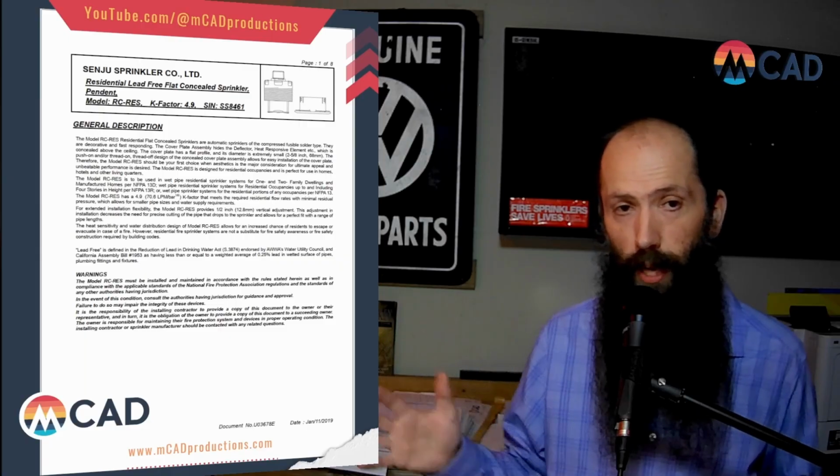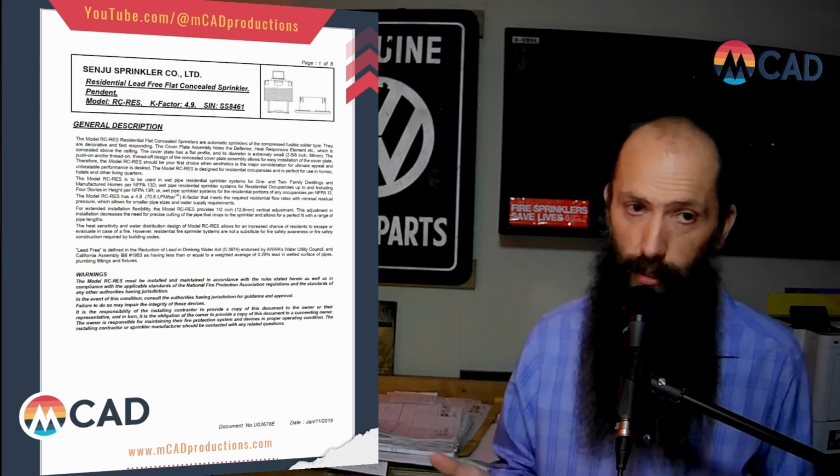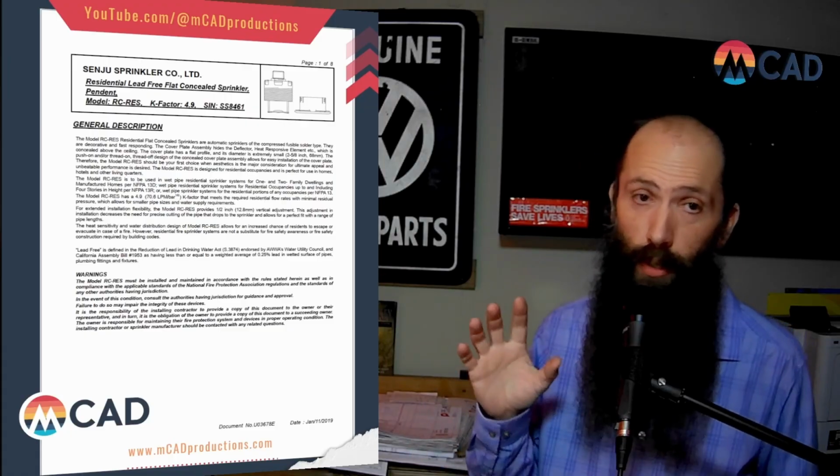If you have a water flow report, you will often be required to supply that with your plans as evidence of the actual water supply being proven that it exists, what you're saying in the calculations. Also, we have to supply a cut sheet of the sprinkler, usually with a 13D system. Typically, that's all the stuff that we have to supply for a 13D system. If we get into 13R, sometimes we might have to do more with 13R, but not necessarily. Usually it's just in 13 where we'll have to provide much more material data.